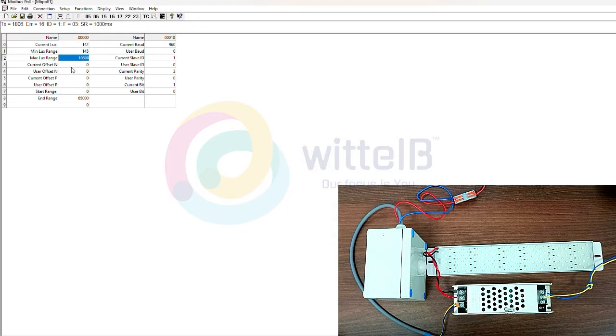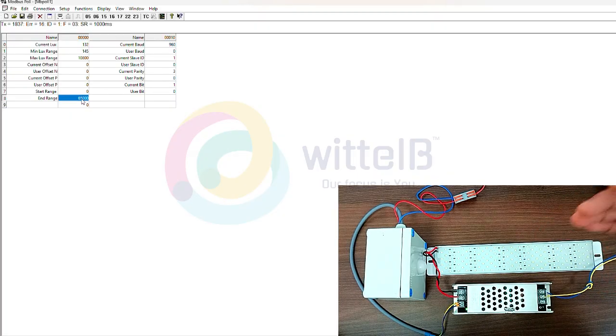Here you can calibrate with an offset value, positive or negative. In the 7th and 8th registers I have provided the starting range and the ending range. The ending range by default is 65,000, but the user can set their own ending range. Currently my Lux maximum range is 10,800. In the end range, I need a value that drives the LED between 9,000 and 10,000. In this range the LED should be driven, so for that I will provide the end range as 10,000.